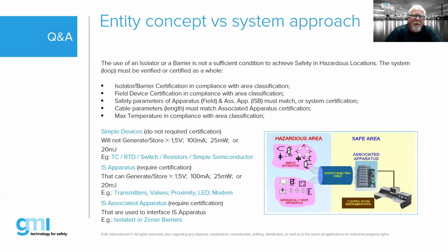There we go. So remember, there are different devices. There's what is called a simple device, right? These do not require certification, and basically we can determine these if they don't generate or store energy in excess of those numbers, then that's a simple device. So a switch, a simple semiconductor, a thermocouple, an RTD, these are simple devices. The IS apparatus that requires certification are items that can store energy. So things like transmitters, valves, proximities, those are all energy storing devices. Again, as we mentioned about cable, we have to take into account the cable parameters and the capacitance, the energy storing of the individual core conductors.